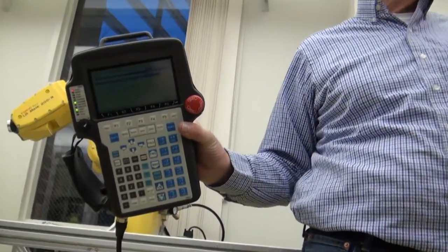Quick master reference and calibrate are the other options in there. Just pick the one you want and follow along — it basically walks you through. Then you have to go back in, say master has been enabled, turn it to off, and mastering is done. Documentation — I do it once a year but I still have to follow this because I can never remember all the paths to the menus. So if you've got documentation, use it. Don't try to do it by memory.